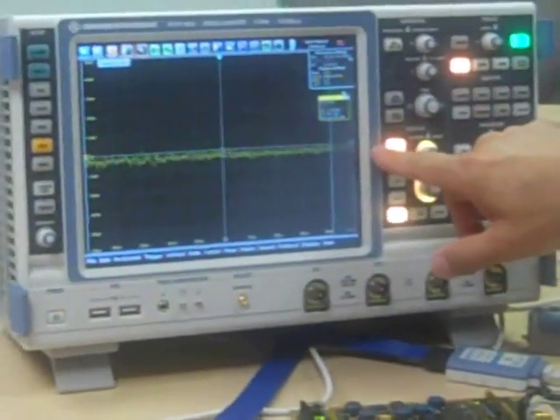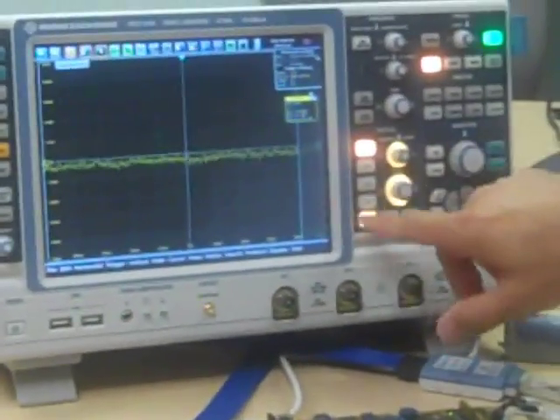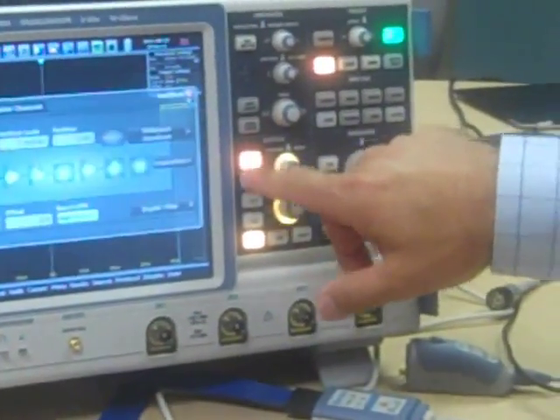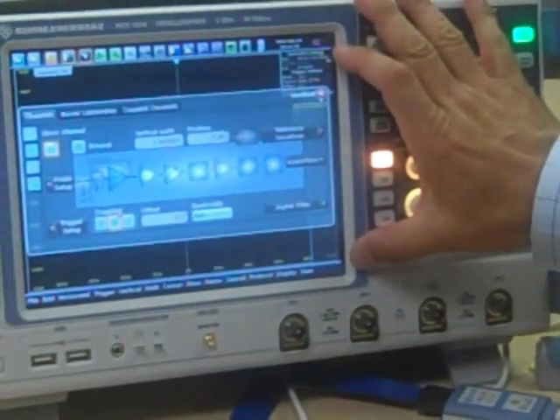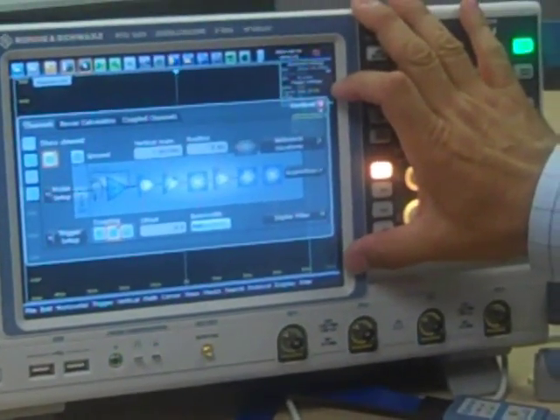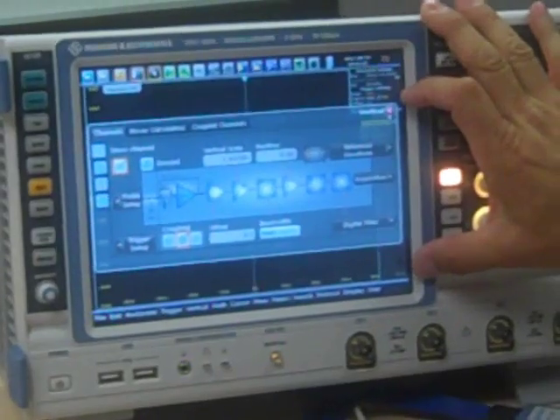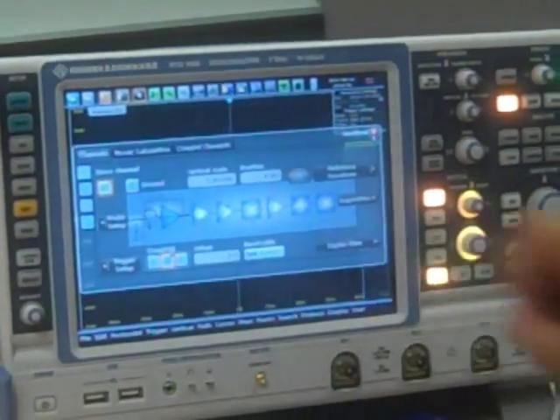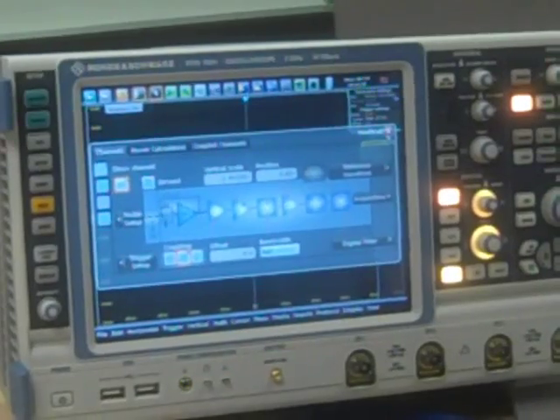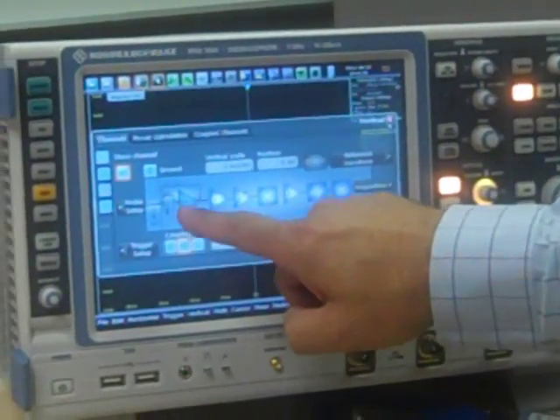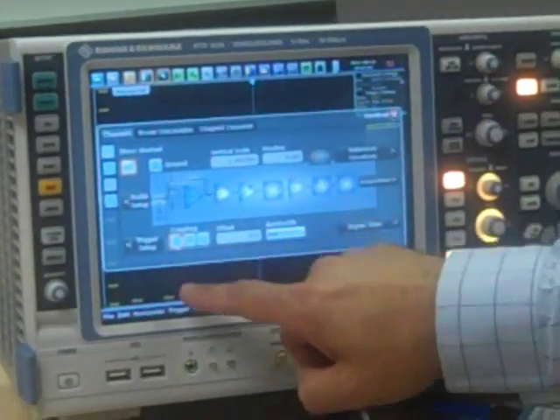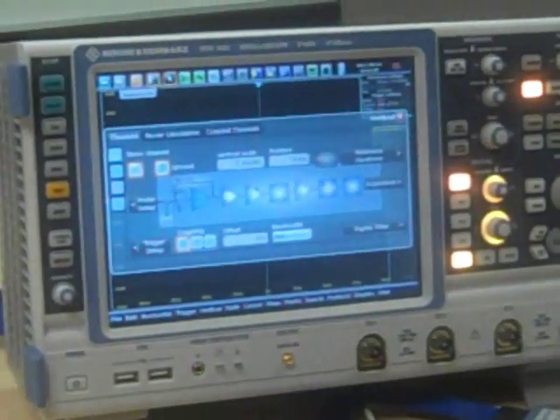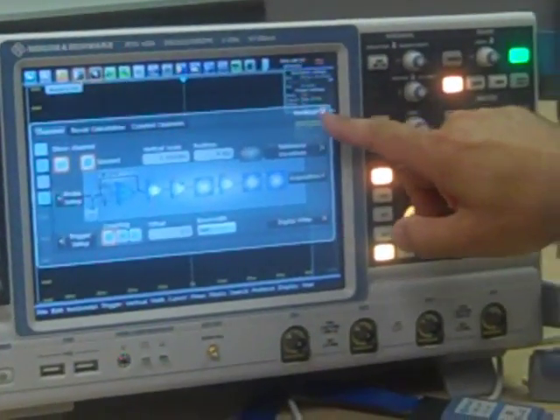I want to set up the front end now so that it's 50 ohms loading. I'm going to go into the menu, and the first thing you'll notice is the menus on the RTO are very graphical in nature, so they not only show where the settings are applied, but actually in the signal chain where each one of the controls affects the waveform. I'm going to switch to DC 50 ohms and ground that input.